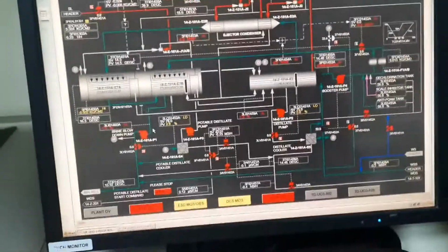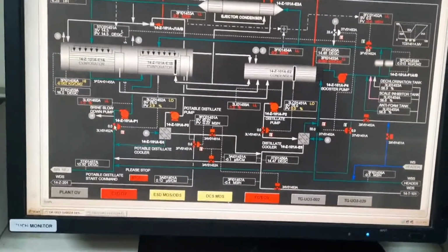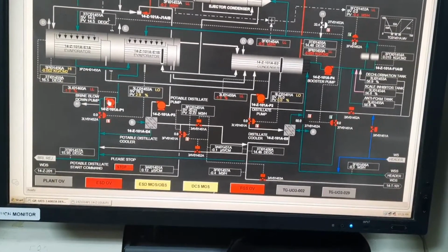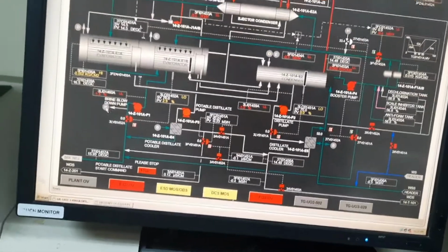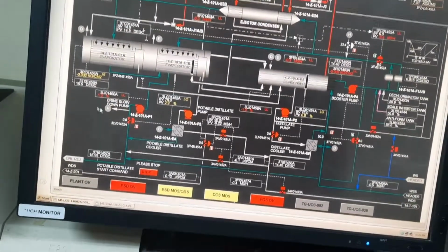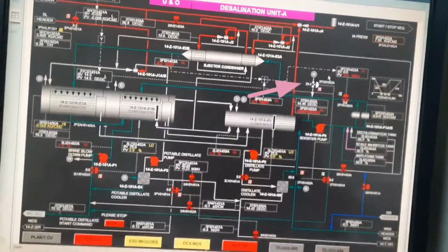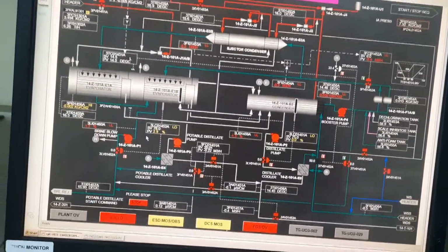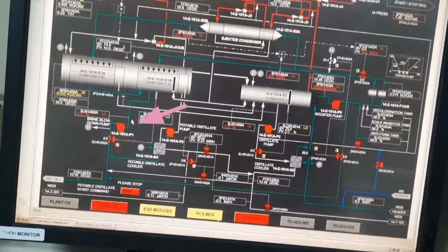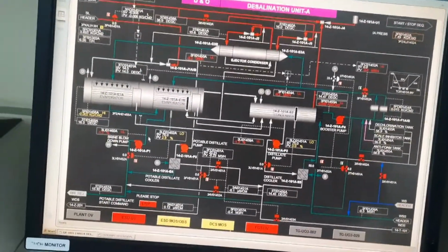Okay. So how will we start acid dosing? Because this circulation is already going on, this control valve is closed. After the brine blow down pump, you see this edge, showing this side. So this circulation water is coming this side. When you start this acid dosing, we will dose this acid to the brine blow down suction side. So when this brine blow down suction valve opens, the acid continues dosing into this circulation water and circulates with this circulation water.